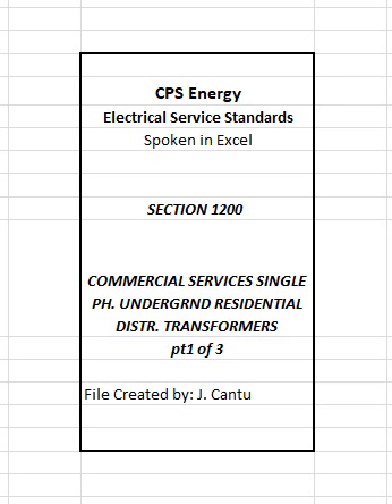1202 Sizing of CPS Energy transformers. Transformer type and size will be determined by the CPS Energy customer service representative based on customer's demand load. 1202-1 Demand loads 250 kVA and under. Where customer's demand load is equal to or less than 250 kVA, a standard single-phase URD type pad mount transformer will be installed/utilized. Note 1. CPS Energy reserves the right to require a compartment type transformer for loads equal to or less than 250 kVA. CPS Energy will require a pour-in-place transformer slab adequate for the compartment type transformer, refer to Article 1204-3, B.